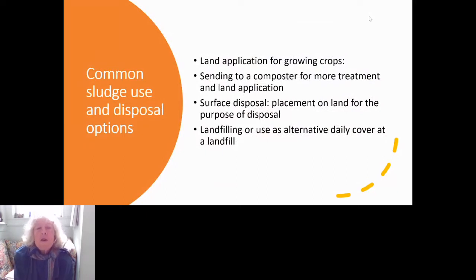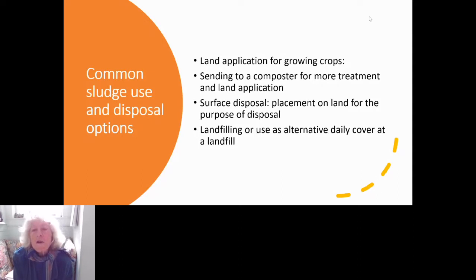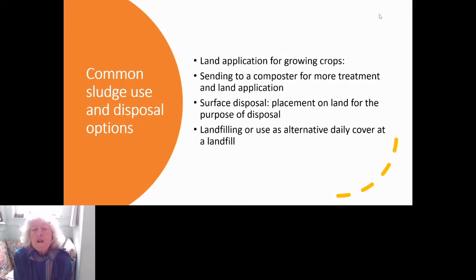There are several options for disposing of sewage sludge and septage. One is land application for growing crops — where you have a specific crop in mind, such as alfalfa or wheat, and apply the sewage or septage for growing it. Another option used by many facilities is sending sludge to a composter who treats it further, then land applies it. Surface disposal means putting sludge on land for the purpose of disposal, not for growing crops.